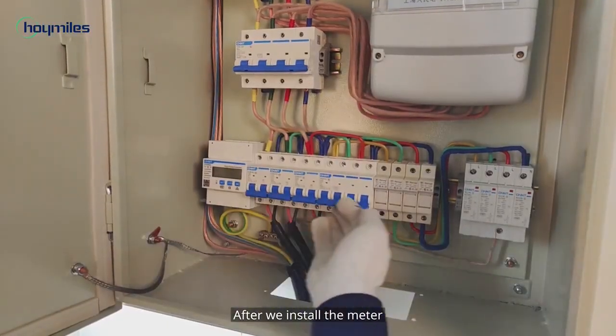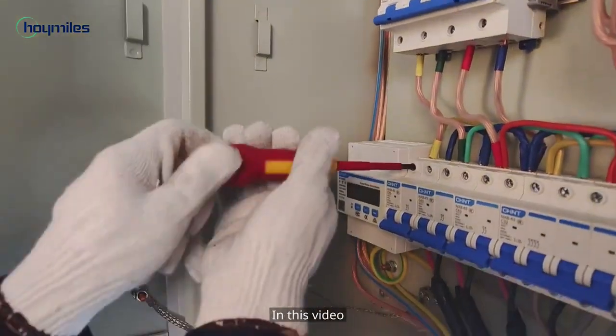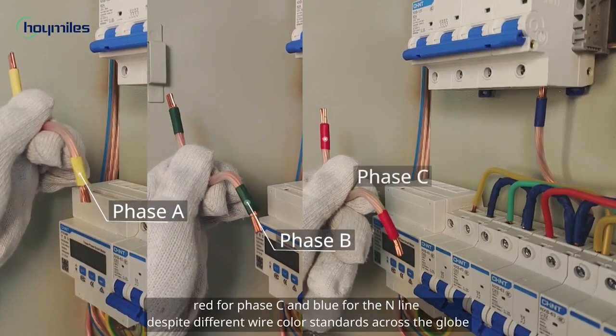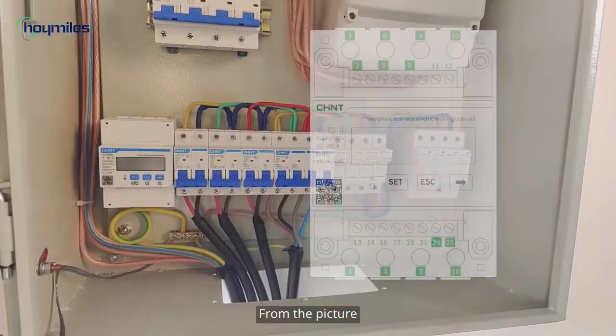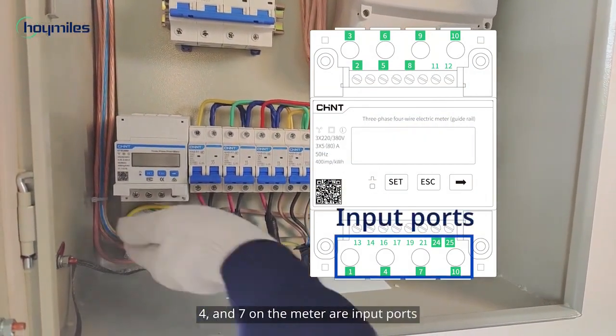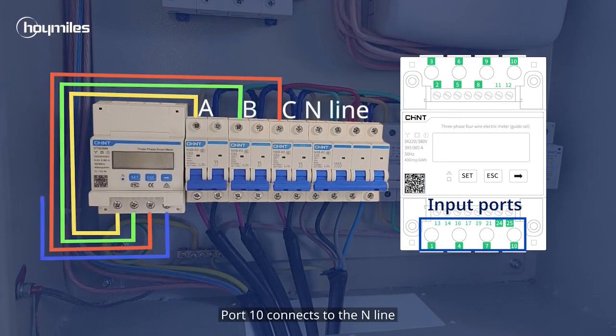After we install the meter, cut off the connection between the main AC breaker and the loads — that is, remove these four wires. In this video, we will use yellow for phase A, green for phase B, red for phase C, and blue for the N line, despite different wire color standards across the globe. Now we come to the connection with each input port of the meter. Ports 1, 4, and 7 on the meter are input ports, which are respectively connected with phase A, phase B, and phase C. Port 10 connects to the neutral line.